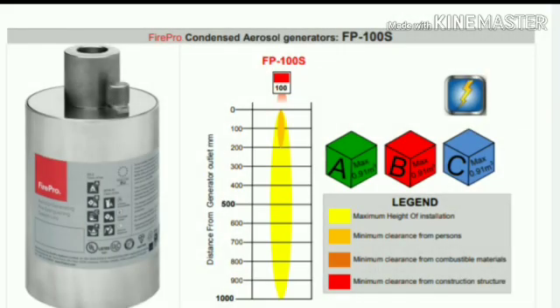Next generator is FP-100S. Activation line supervision current maximum: 5 mA. Aerosol discharge time: minimum 5 seconds, maximum 10 seconds. Generator dimensions: height 155 mm, diameter 84 mm. Self-activation temperature of FPC: 300 degrees. Class of fire: NFPA 2010 ABC. Generator coverage constraints: minimum height 0.45 m, maximum area 2.65 m², maximum throw 1.82 m. Maximum height of installation: 1 meter. Minimum clearance from person: 200 mm. From combustible materials: not required. From generator casing: 6.4 mm.